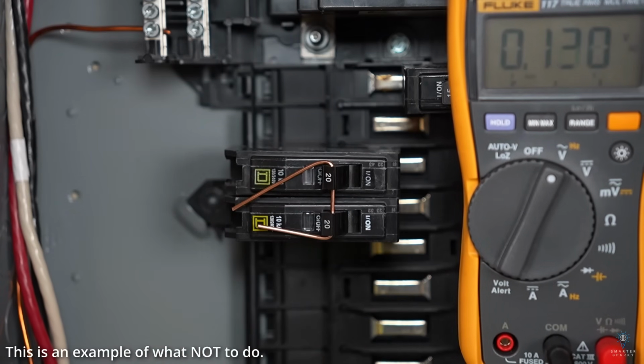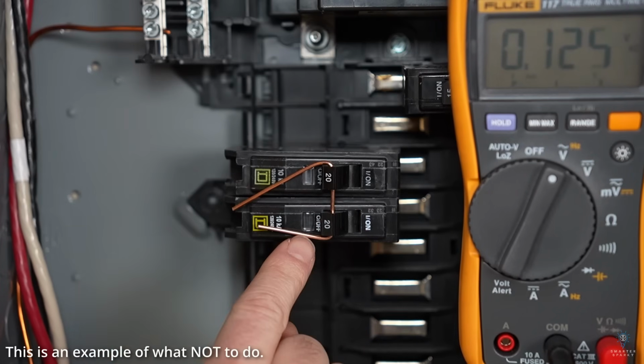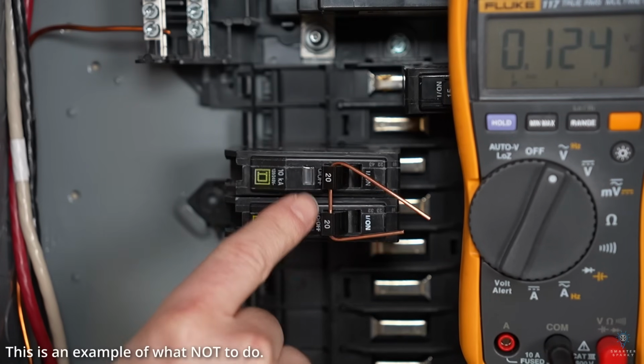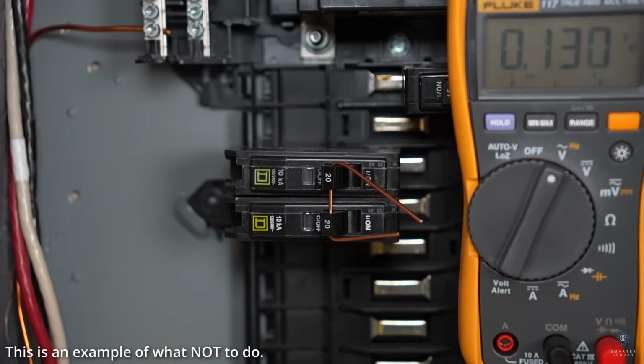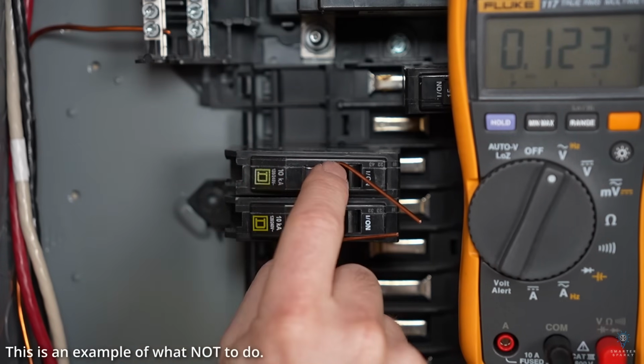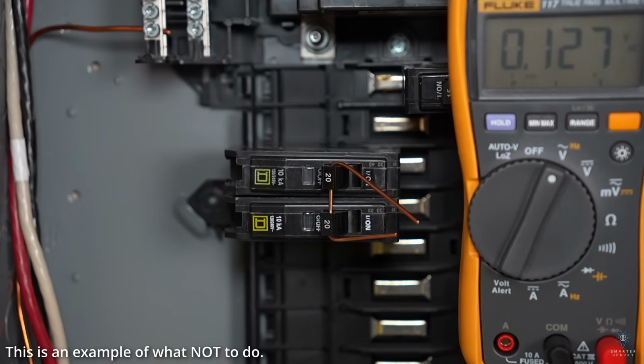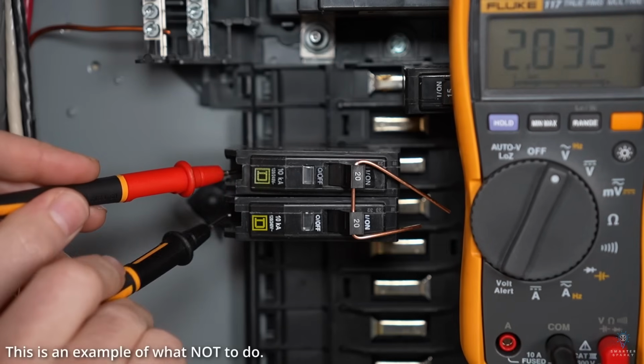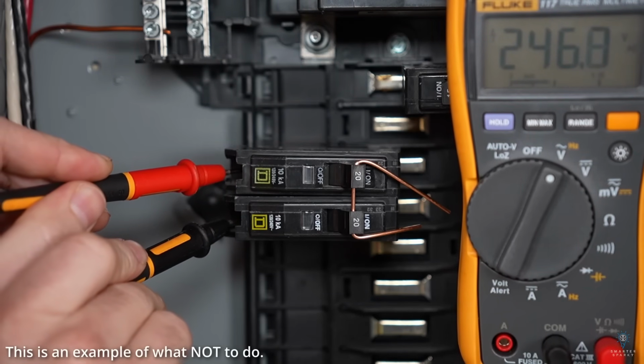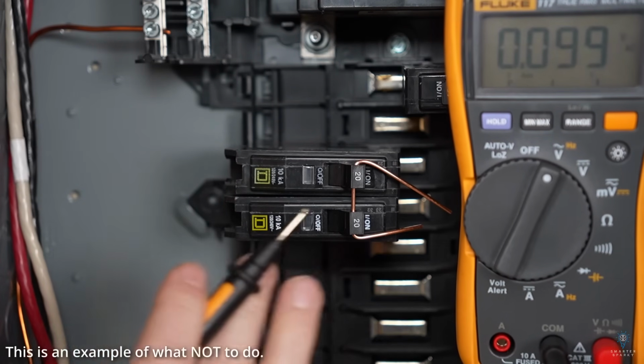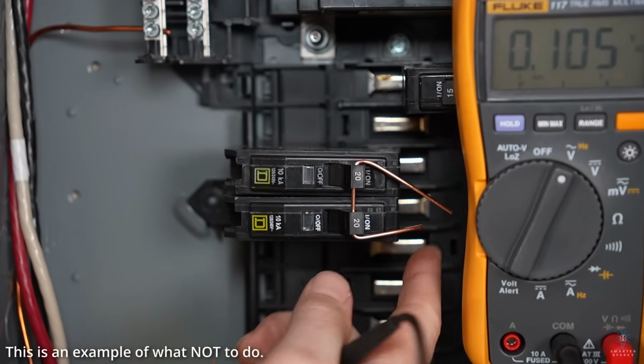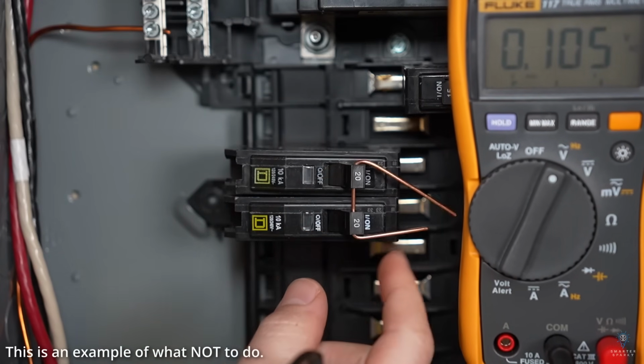Sure, you could give it a try, but here's the problem. There is no way for you to guarantee that whatever you put between those 2 breakers is going to ensure that those 2 breakers trip together. That's why it is not okay to use 2 single-pole breakers in order to get 240 volts. Will it work? Sure, you get 240 volts. Is it safe? Absolutely not. Don't do this. This I see out in the field all the time.